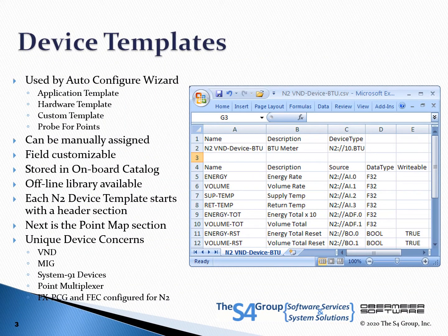The Configure Wizard utilizes hardware device templates, application-specific device templates, and custom device templates to prepare for publishing to BACnet IP. When a match is not found, the Configure Wizard has the ability to drill down into devices and probe them for points. Computer-generated names are assigned to each readable point.